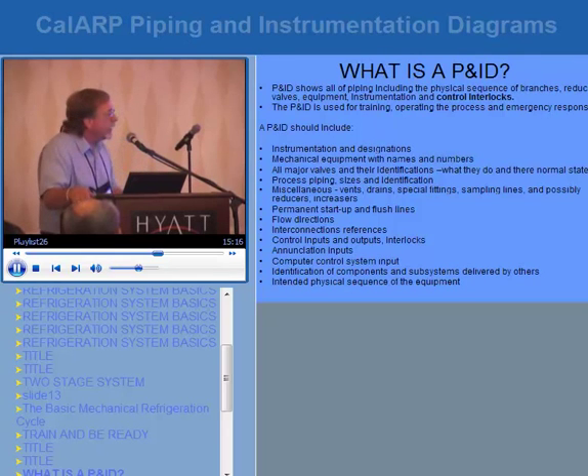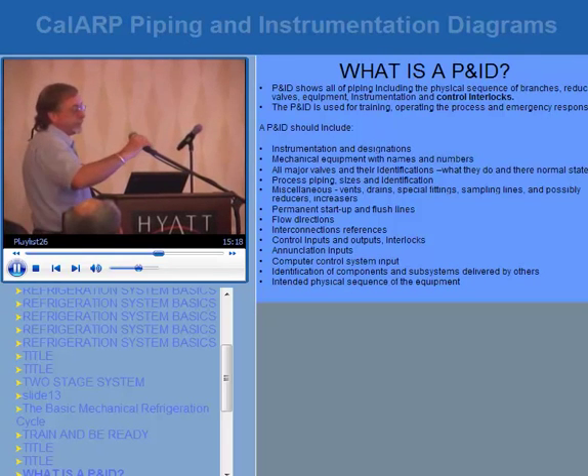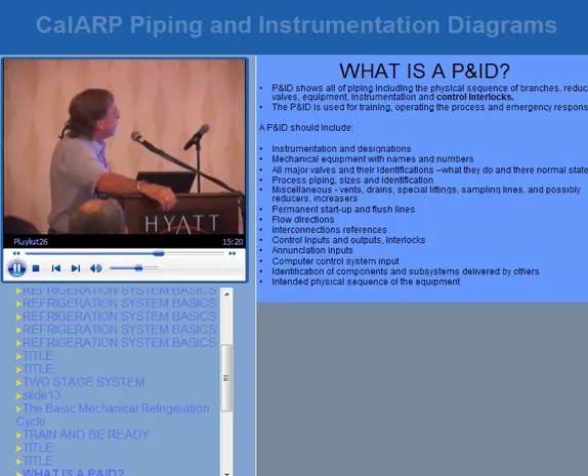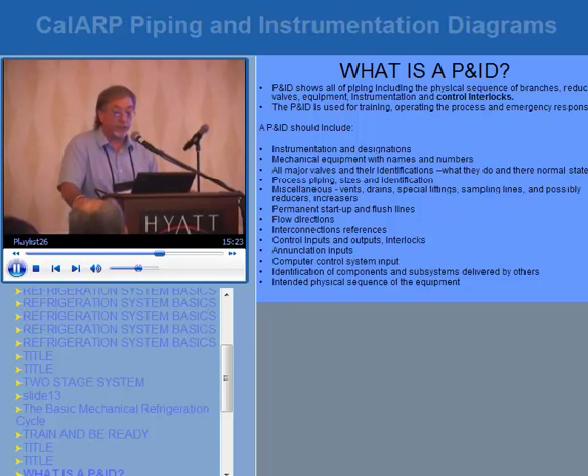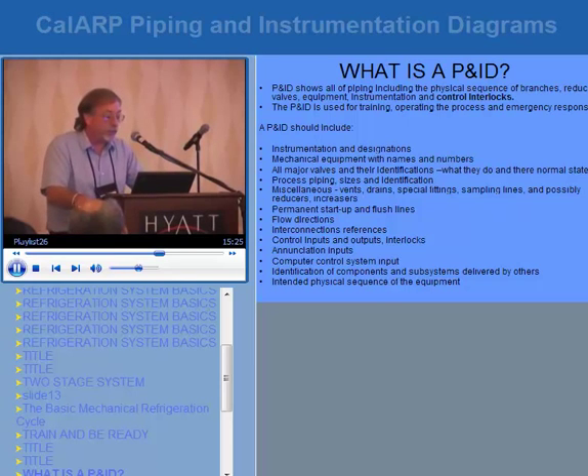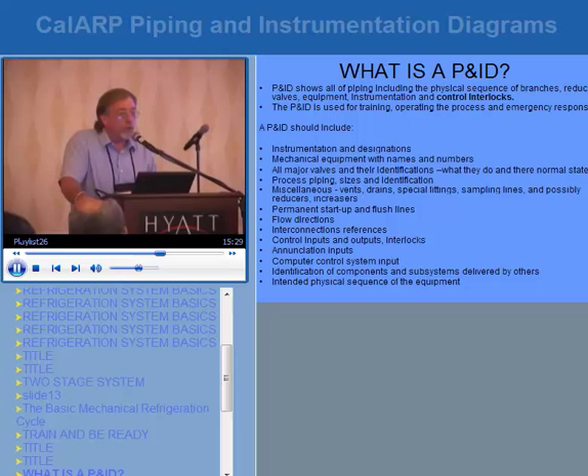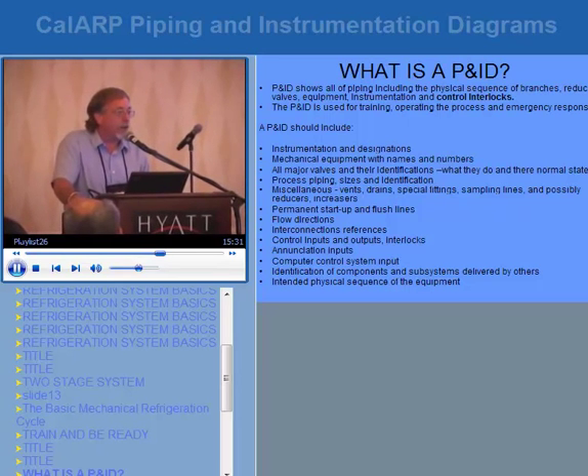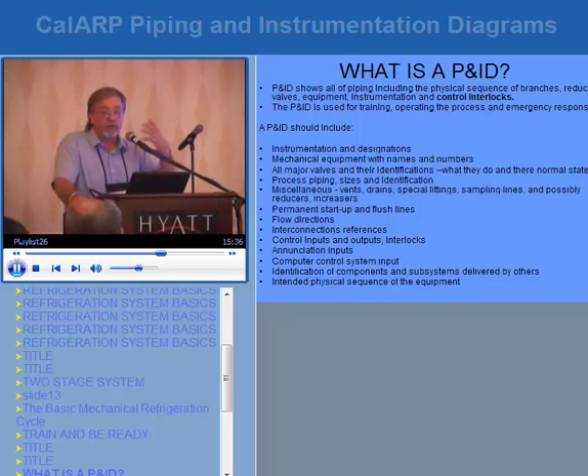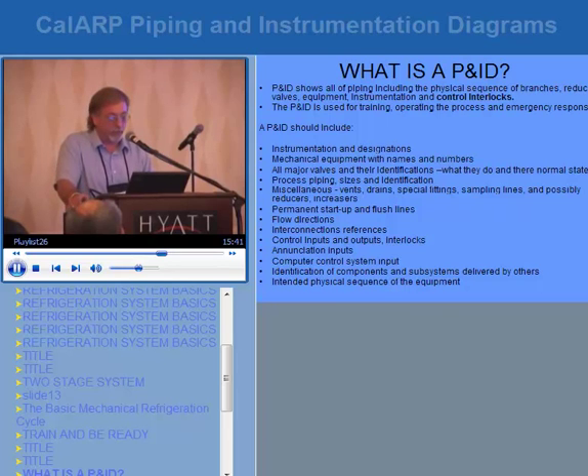So what is a P&ID? P&IDs show all of the piping, including the physical sequence of branches, reducers, valves, equipment, instrumentation, and control interlocks. Where we're lacking in a lot of P&IDs are the interlocks — the safety controls — what a float does, what a solenoid does, the actual controls of the system, because we have both manual and automatic controls in refrigeration. The P&ID is used for training, operating the process, and emergency response.